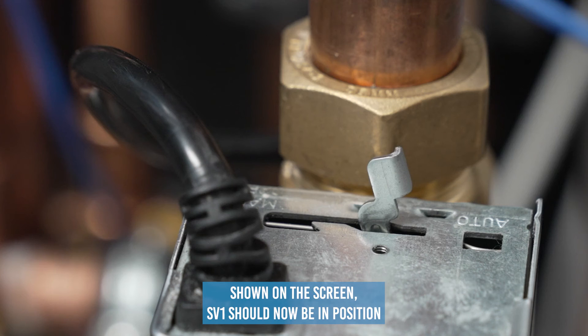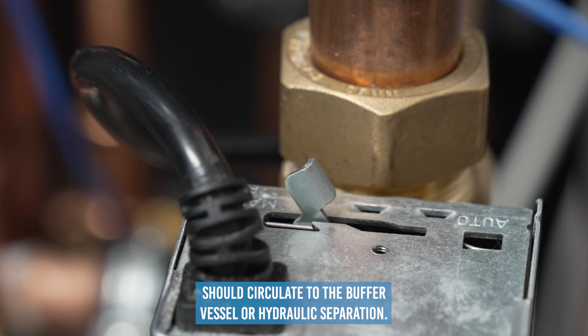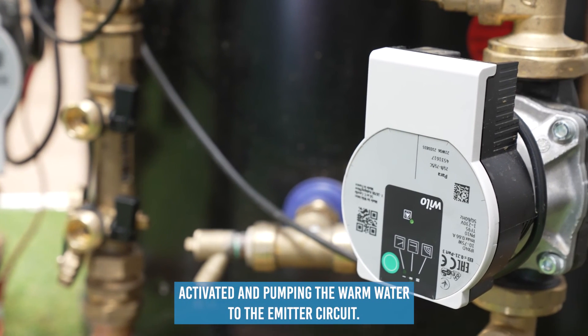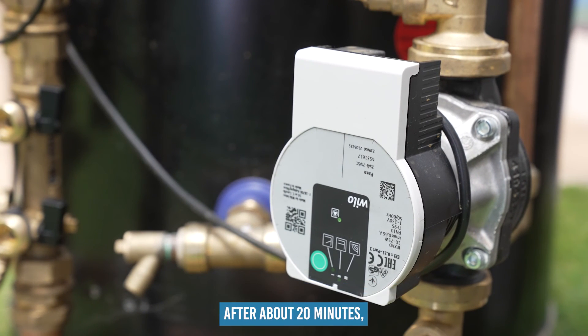SV1 should now be in position B, and the hot water produced by the heat pump should circulate to the buffer vessel or hydraulic separator. Pump O should now be activated and pumping the warm water to the emitter circuit. Once again, please complete the commissioning data after about 20 minutes.